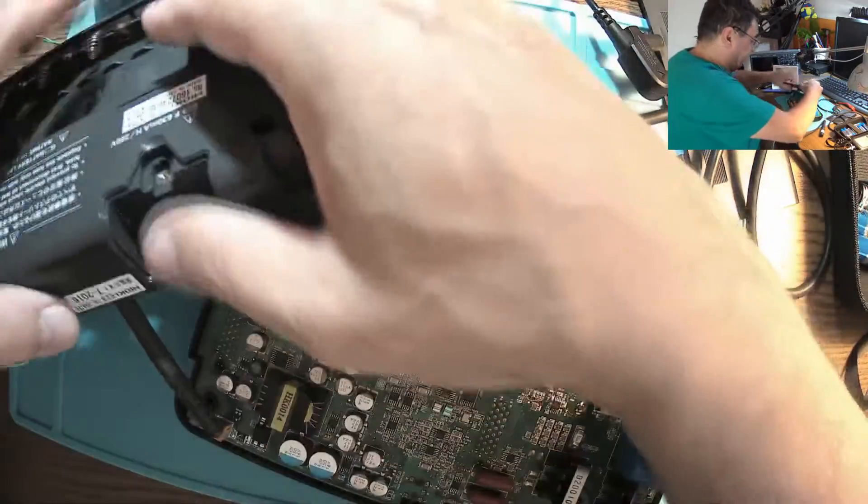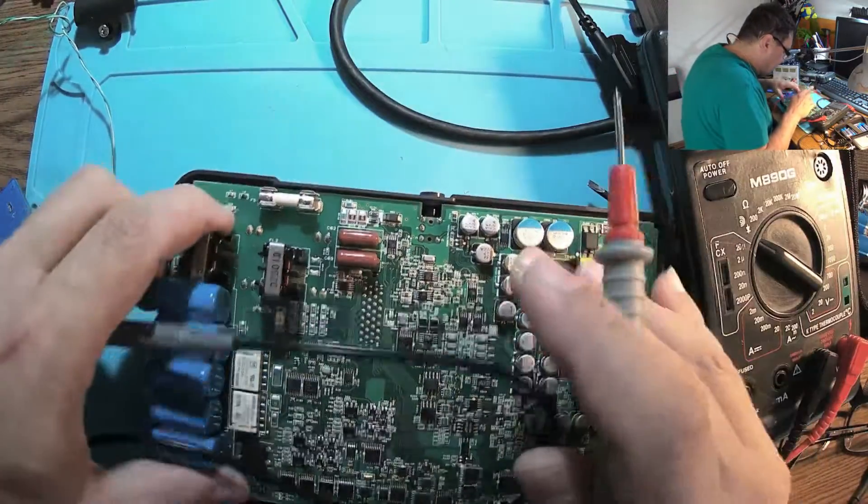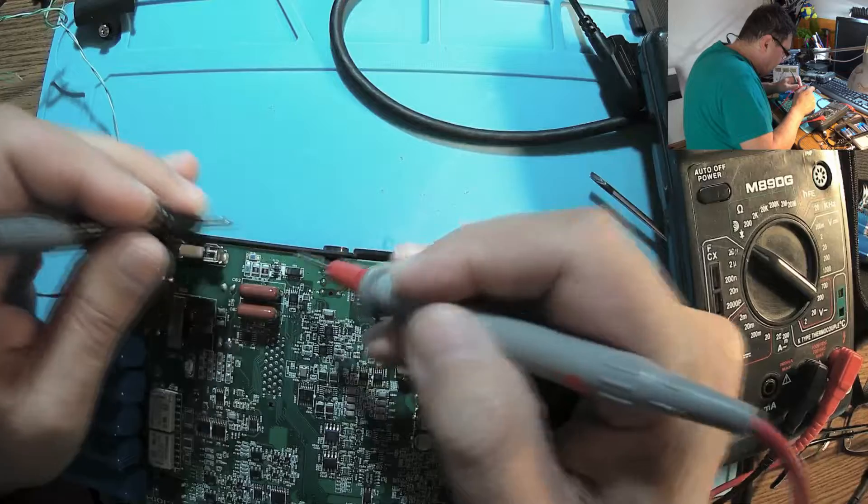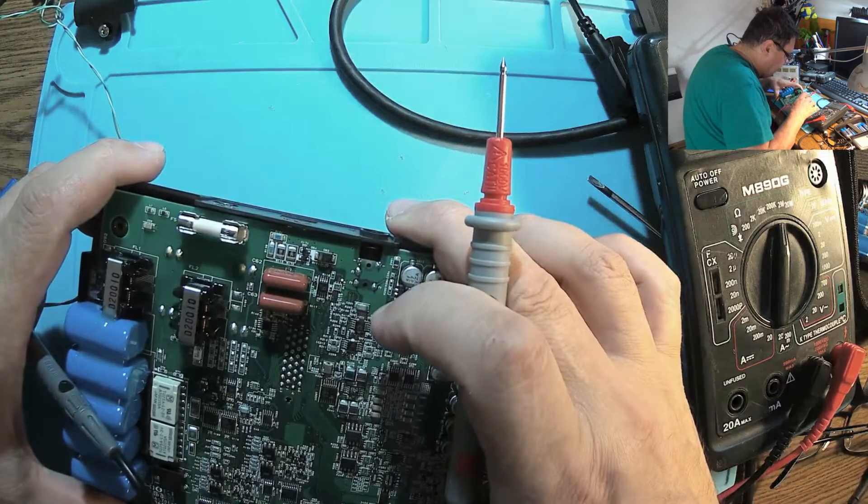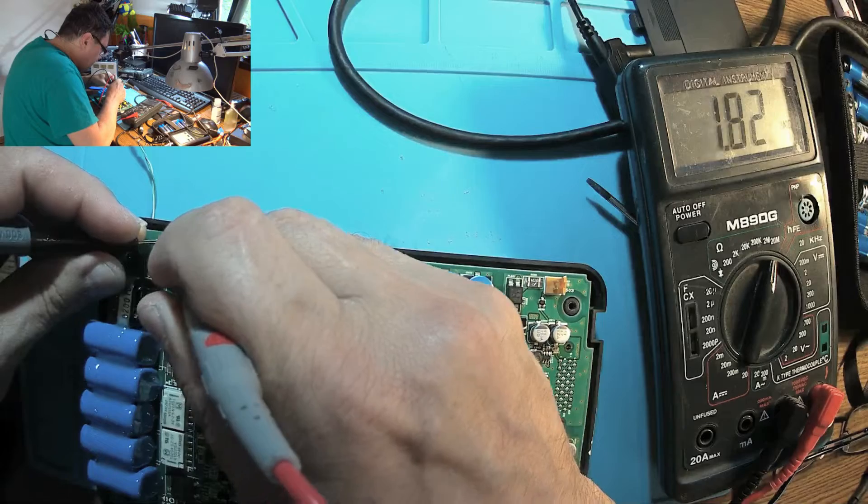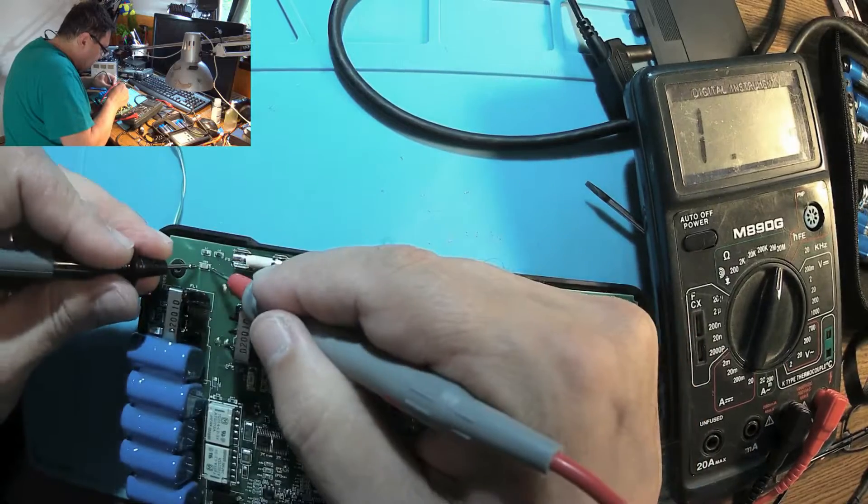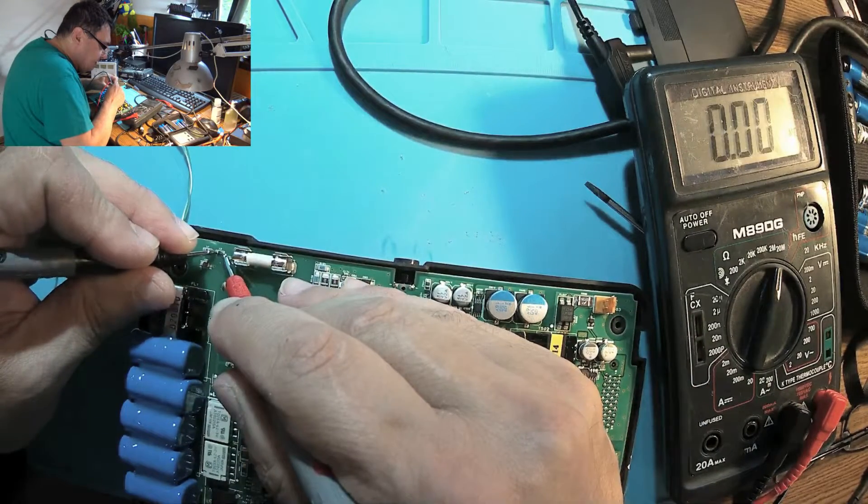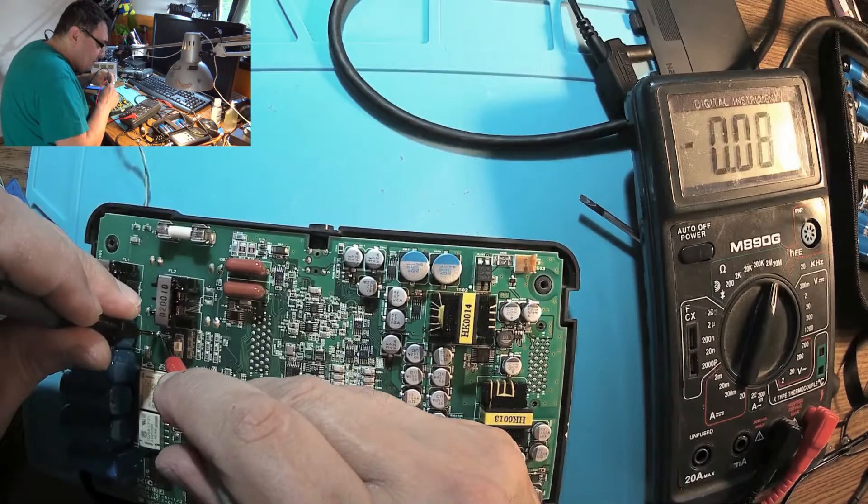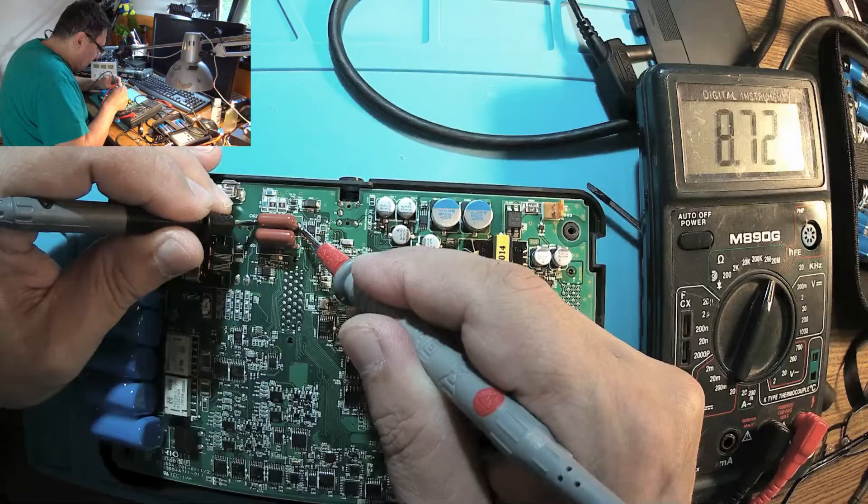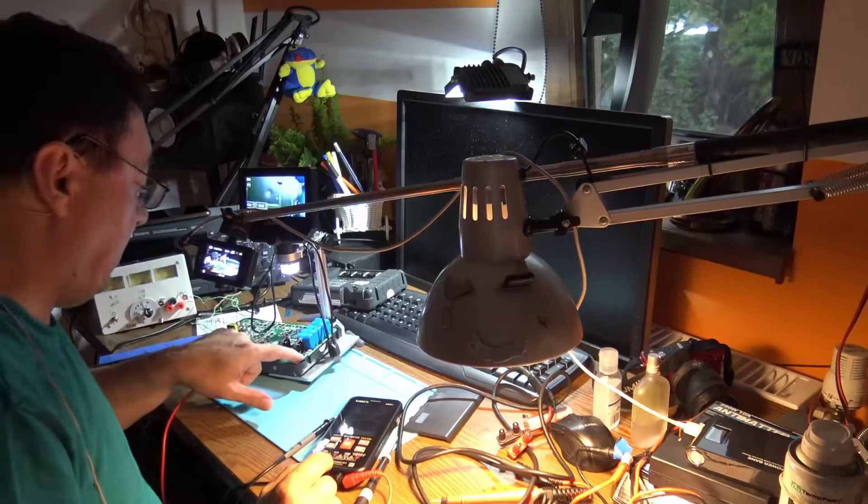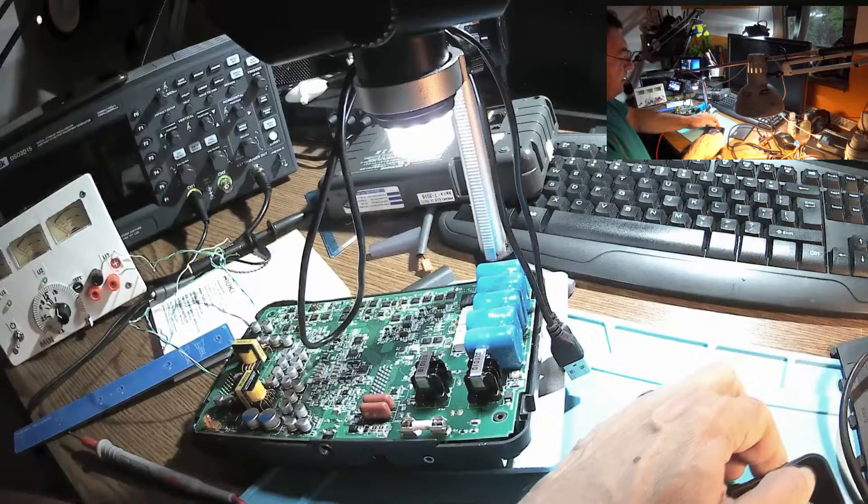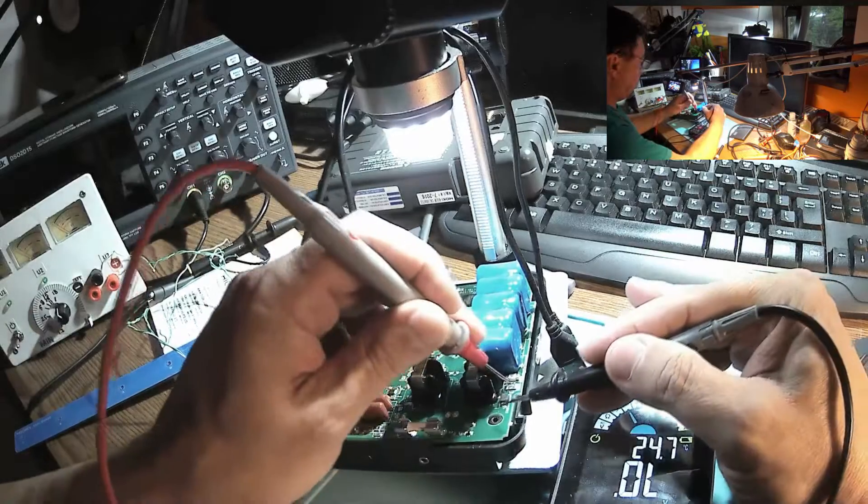There we go. Multimeter in diode mode. Let's check those diodes here first. This little guy, this is good. This is good. These guys are okay and this one, it's okay too. So we have a few resistors here, 3304. We have a coil here which is good. Have another one, that's an L5. Okay, I believe we have a coil right here which gives me, oh no it's zero, it's okay, it's an error. Another fuse here, one amp. And we have another coil. Okay, this is good. About these capacitors, fine. I'm looking for shorts. And we have an area of resistors here, one megaohm. So far I found one of these diodes having no readings both ways.